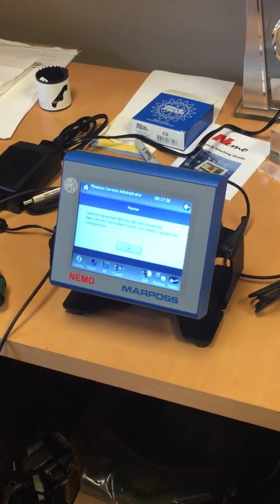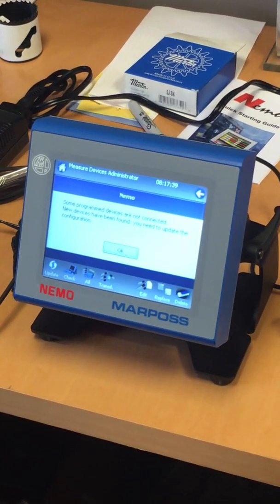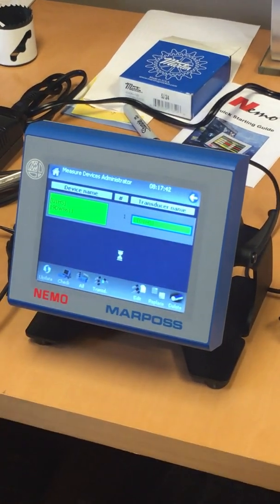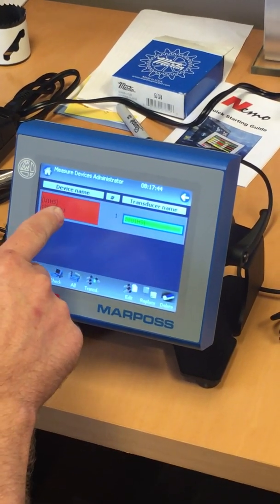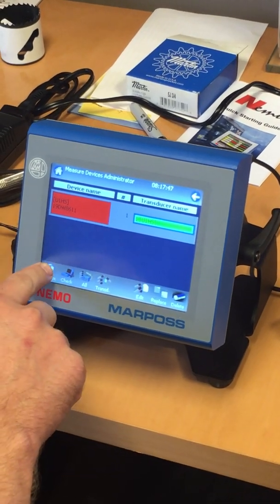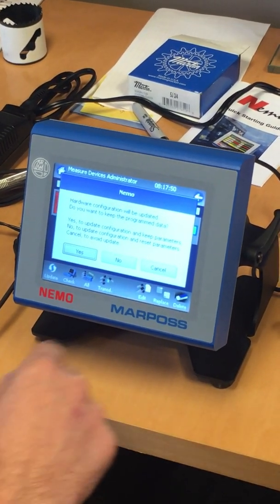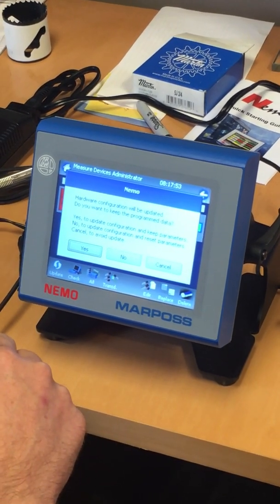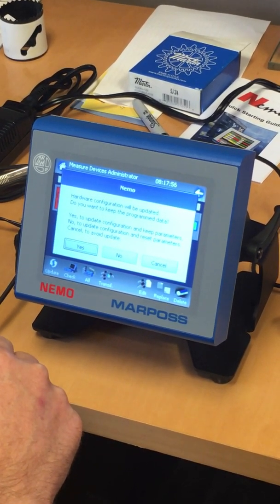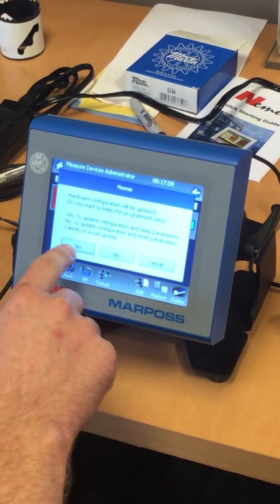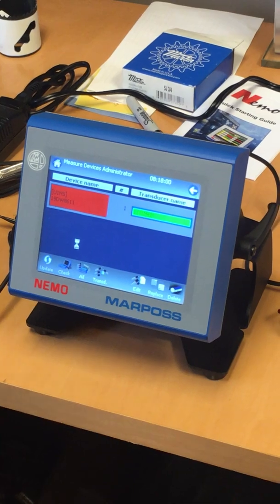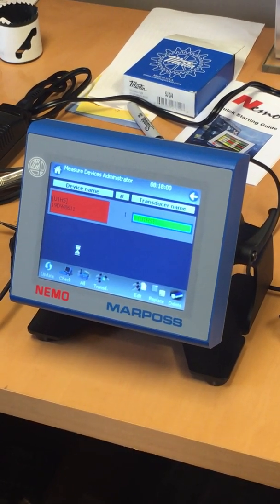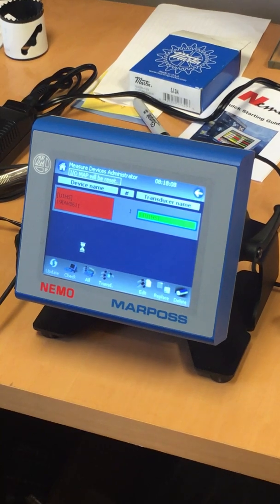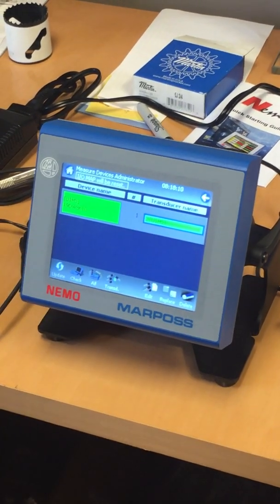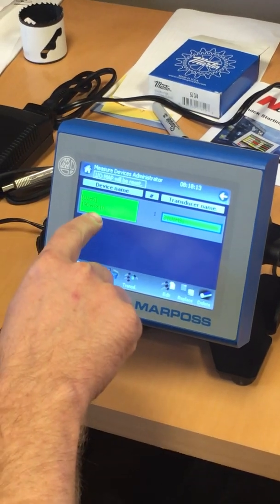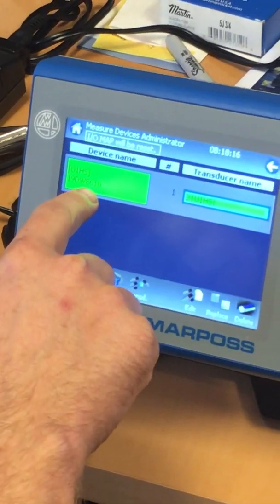At this point, the NEMO should recognize that a new device is found and you need to update the configuration. Hit OK. Your device name will now be in red. Select the update button. The NEMO will then prompt you to ask if you want to keep the parameters or reset parameters. Go ahead and say yes to keep configuration. Once complete, the device name will become green again. The number in the bottom will be the serial number of the LVDT that you've replaced.